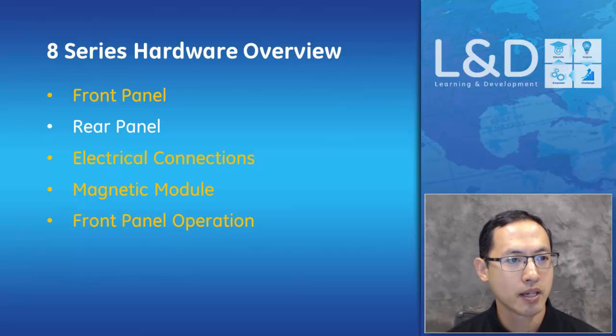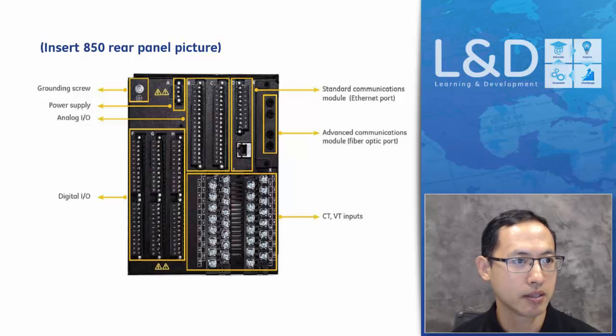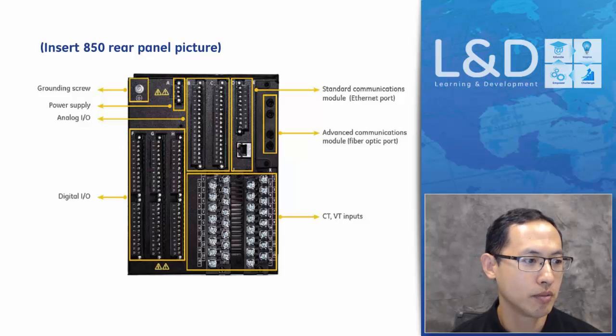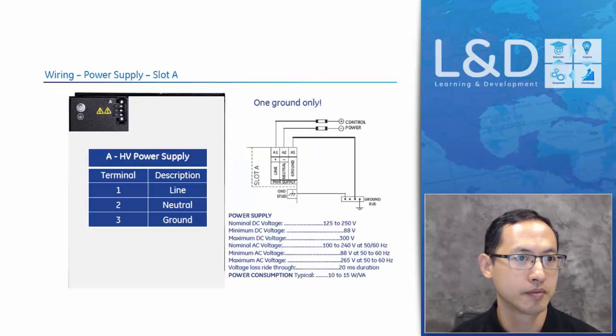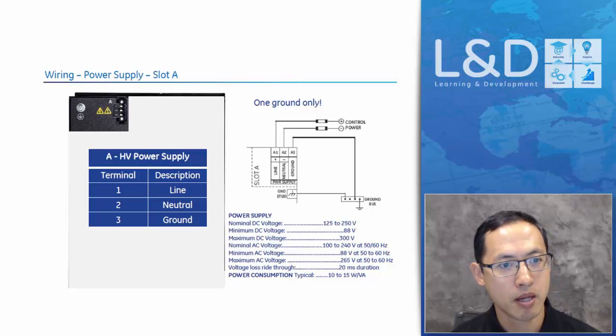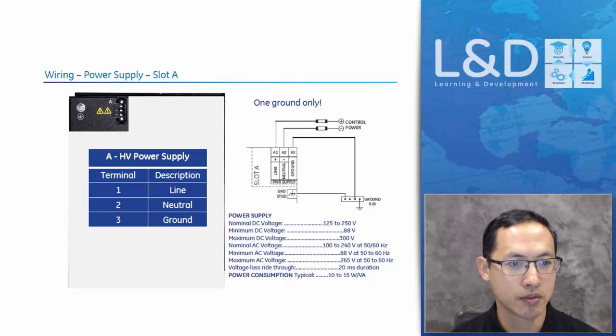So now let's see the rear side of the relay. On the rear side, we can see the grounding screws, the power supplies, low voltage I/Os, communication ports, high voltage I/Os, and analog CT/VT inputs. The first is the grounding and the power supply. We can see now this uses only one ground for this 8 Series, unlike the SR relays that need 2 grounds. And the power supply has a DC range of 125 to 250, and an AC range of 100 to 240, 50 and 60 Hertz.